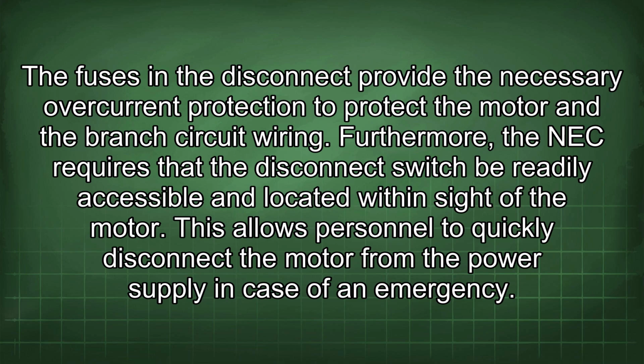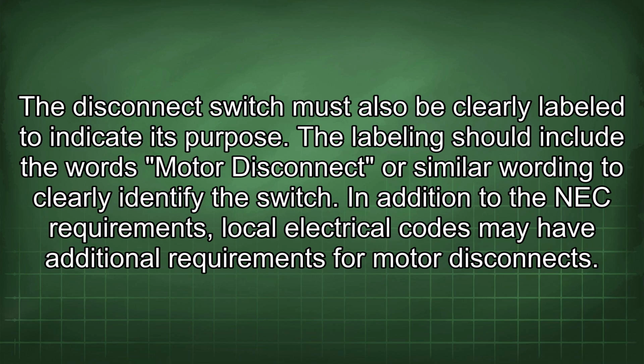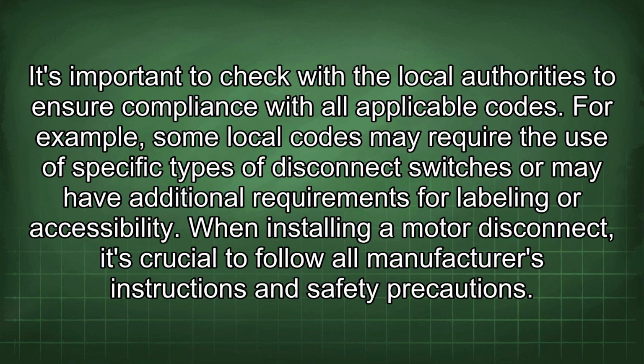Fuses in the disconnect provide the necessary overcurrent protection to protect the motor and the branch circuit wiring. Furthermore, the NEC requires that the disconnect switch be readily accessible and located within sight of the motor. This allows personnel to quickly disconnect the motor from the power supply in case of an emergency. The disconnect switch must also be clearly labeled to indicate its purpose. The labeling should include the words motor disconnect or similar wording to clearly identify the switch. In addition to the NEC requirements, local electrical codes may have additional requirements for motor disconnects. It's important to check with the local authorities to ensure compliance with all applicable codes.